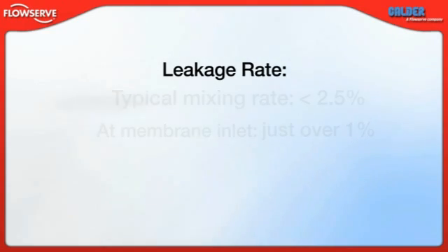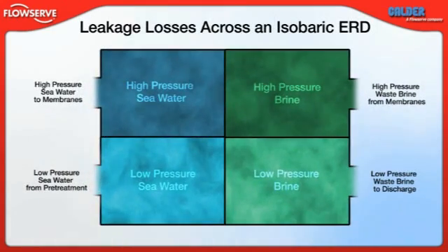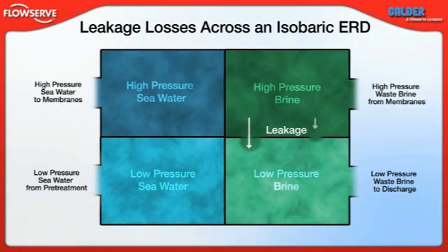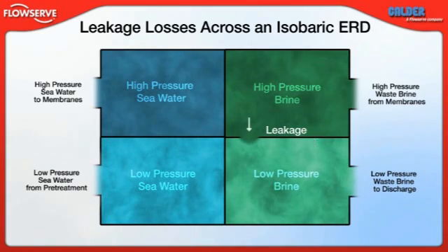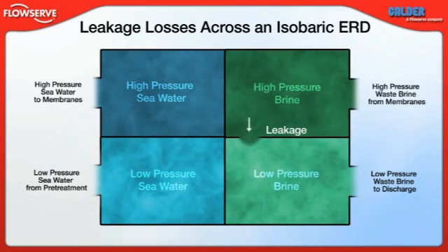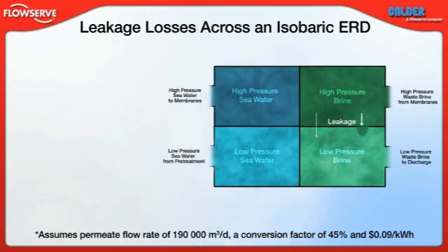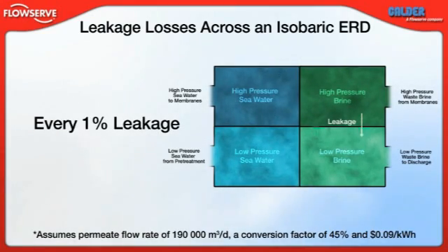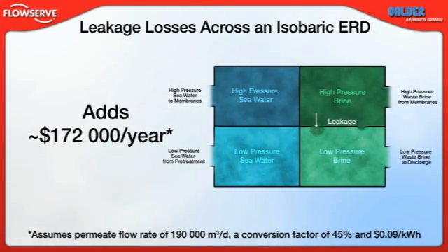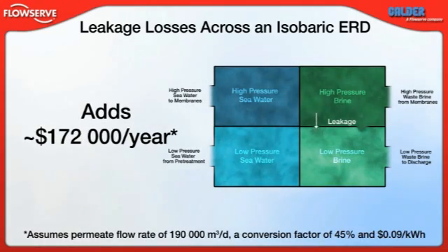The DWIR's leakage rate is also very low — less than 0.4% of the incoming high pressure brine flow. Sometimes called lubrication flow, leakage refers to the direct discharge of high pressure brine. The net effect of lubrication flow is a reduction in the amount of high pressure brine from which energy can be extracted. To compensate, the high pressure feed pump must produce higher flow, consuming additional power. Using the same example of 190,000 cubic meters per day and 9 cents per kilowatt hour, every 1% leakage over an isobaric ERD adds about $172,000 USD to the operating cost. With its low mixing and leakage rates, the DWIR provides plant owners and operators high recovery rates while minimizing operating costs.